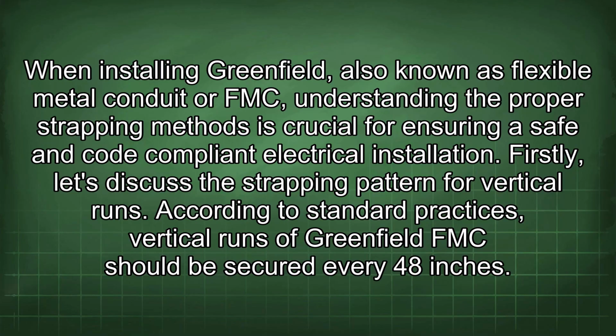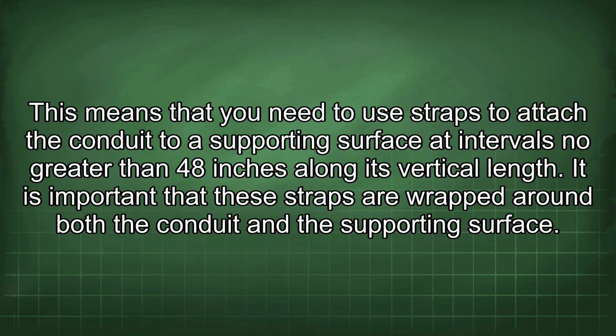When installing Greenfield, also known as flexible metal conduit or FMC, understanding the proper strapping methods is crucial for ensuring a safe and code-compliant electrical installation. Firstly, let's discuss the strapping pattern for vertical runs. According to standard practices, vertical runs of Greenfield FMC should be secured every 48 inches. This means that you need to use straps to attach the conduit to a supporting surface at intervals no greater than 48 inches along its vertical length.